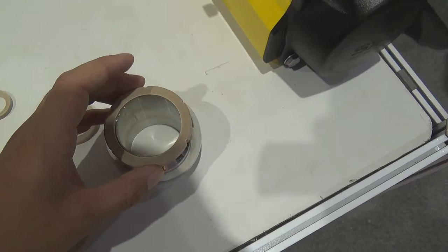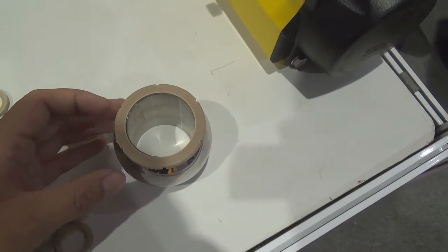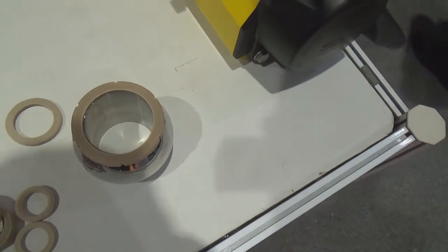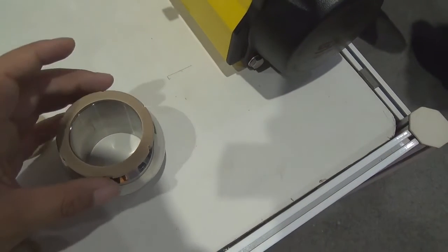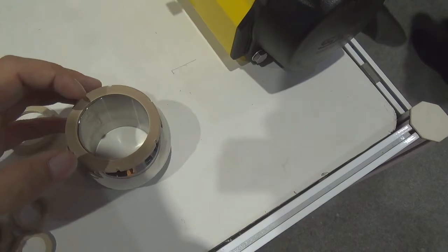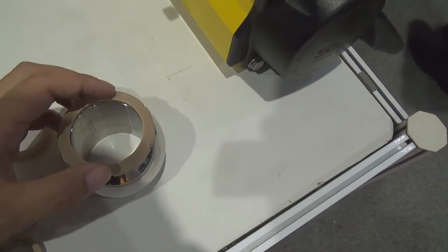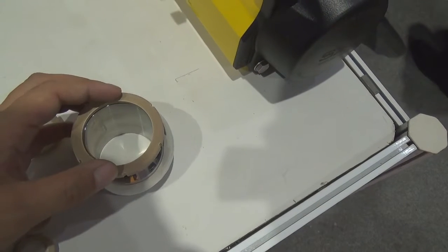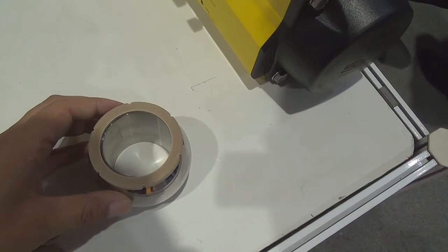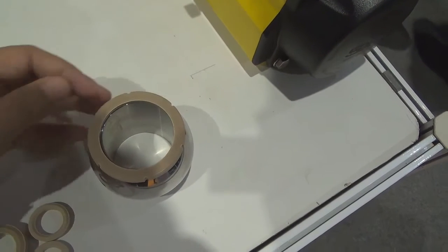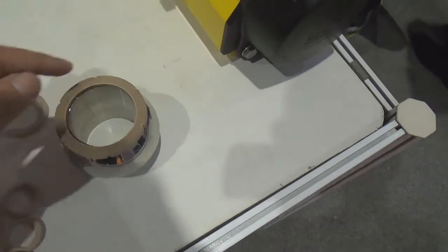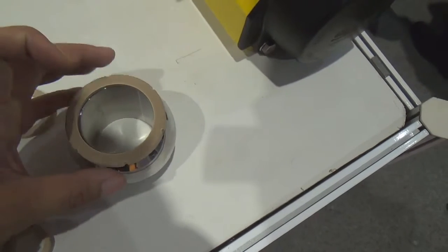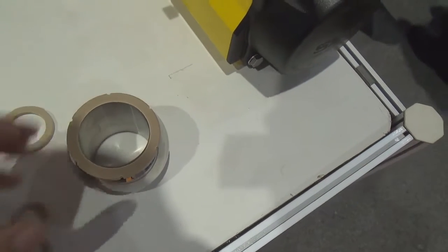And when we use this kind of soft seat ball valve, the reason why we produce several grooves on the outside of the valve seat, I already talked about before. When we use this kind of valve seat, if the pressure flows to the back of the valve seat, the pressure will push the valve seat against the ball. If the valve is closed for a very long time, the valve seat will have permanent deformation. So that is the reason why we cut several grooves on the outside of the valve seat. So the pressure will flow to the cavity to relieve the pressure. So the valve seat will be safe.